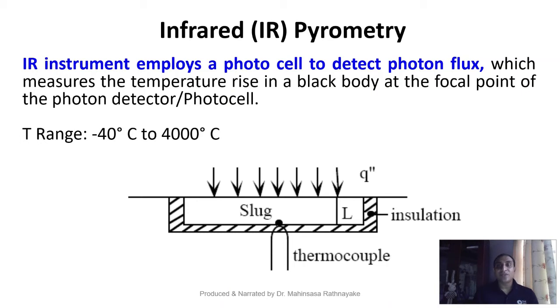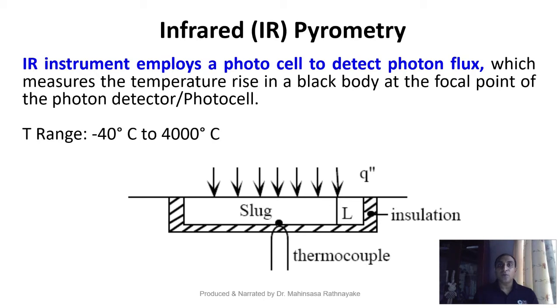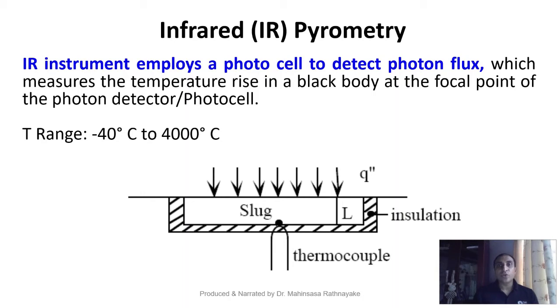The third type is the infrared pyrometer, which is widely used today as a mobile thermometer. It employs a photo cell to detect photon flux from the incoming radiation rather than using traditional lenses, and measures the temperature of the source based on that flux. Sometimes lenses are added to focus the radiation. The temperature range of IR pyrometers is also quite large: minus 40 to 4000 degrees Celsius.